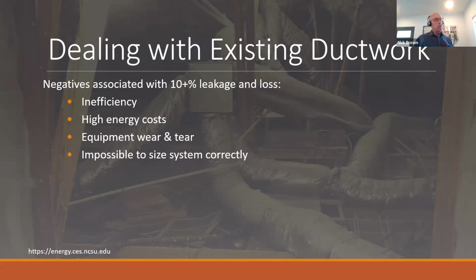Negatives associated with duct leakage include inefficiency and high energy costs, but also your fan's working more than it needs to. And as Bobby said, that ductwork has been carefully designed to put a certain amount of air in each room to provide for comfort. As soon as you start having leakage, you have no predictability on where your conditioned air is going, and you're going to have certain rooms at the tail end of the ductwork just not getting enough conditioned air.